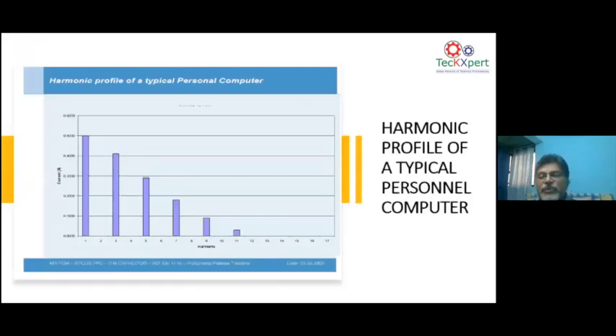Now, again, if you look into the frequency spectrum of the harmonics produced, because when you say harmonics produced, it has two aspects. One is the time domain: as the harmonic progresses as a time function, it has a magnitude, and it keeps varying. If you have a third harmonic, it has a certain magnitude. If it's a fifth, it has a certain magnitude. And based on the time function, from 0 to a cycle, it keeps varying. But if you take it in the frequency domain, you can split it in terms of the frequencies contained in that wave.